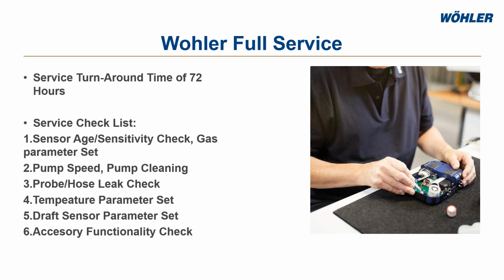And then they're going to check the pump speed. If there's any debris or dirt or moisture buildup, they're going to clean that pump out completely. So they're going to make sure that the pump in the analyzer is running the way it should be. If it's not, they're going to replace it for you. They're going to check the probe and hose, make sure there's no leaks in there. Like we said earlier, it's really important that the hose and the probe has a tight seal connection so there's no ambient air seeping in and affecting any readings on your analyzer.